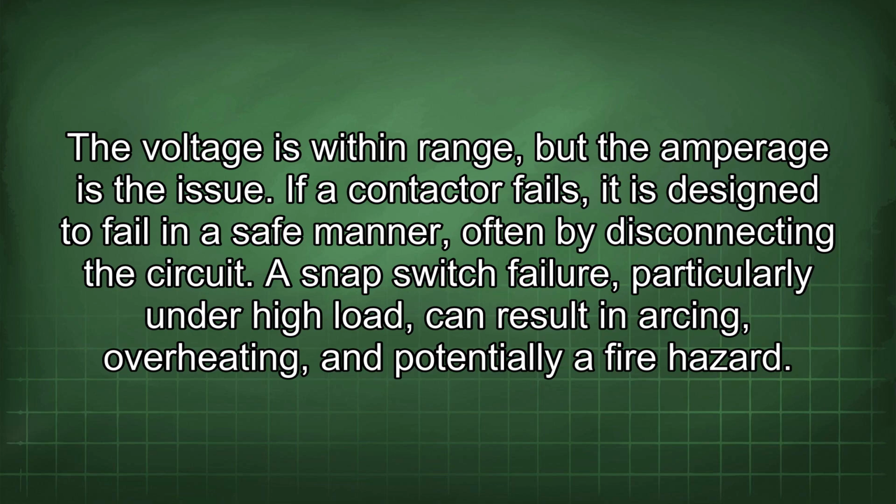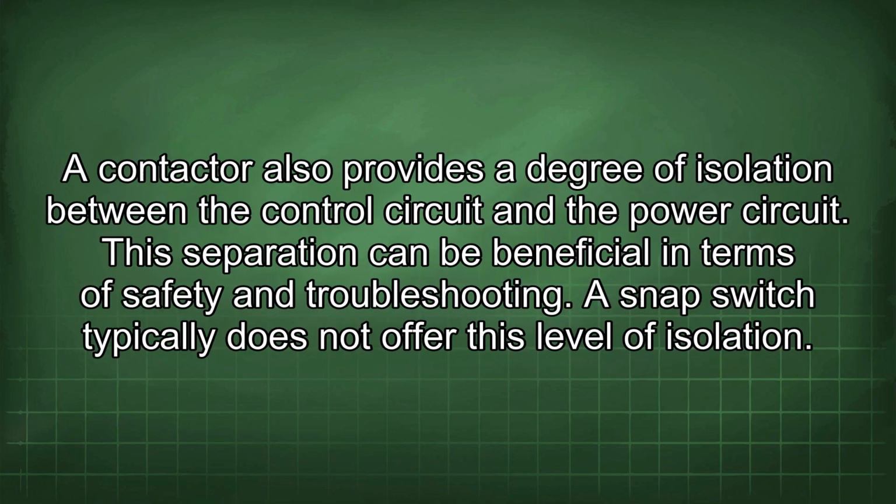If a contactor fails, it is designed to fail in a safe manner, often by disconnecting the circuit. A snap switch failure, particularly under high load, can result in arcing, overheating, and potentially a fire hazard. A contactor also provides a degree of isolation between the control circuit and the power circuit. This separation can be beneficial in terms of safety and troubleshooting. A snap switch typically does not offer this level of isolation.